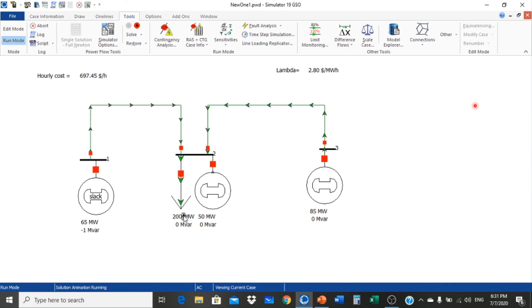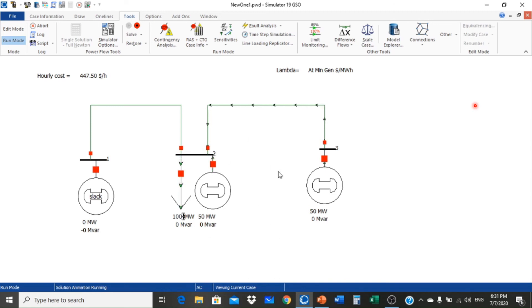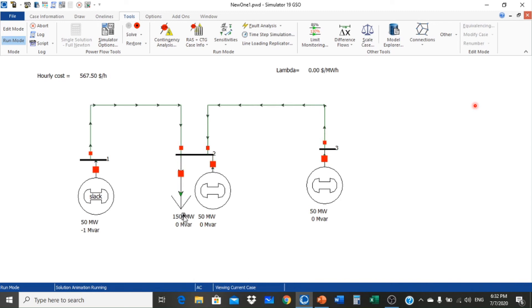At 100 megawatt load, only two generators are supplying power. Generator 1 is switched off giving zero megawatt; generators 2 and 3 supply power to meet the 100 MW load. The hourly cost at 100 MW is $447.50 per hour, and lambda is at minimum generation. Note that the system should not normally run below 150 MW, but we are running at 100 MW so lambda is at minimum.